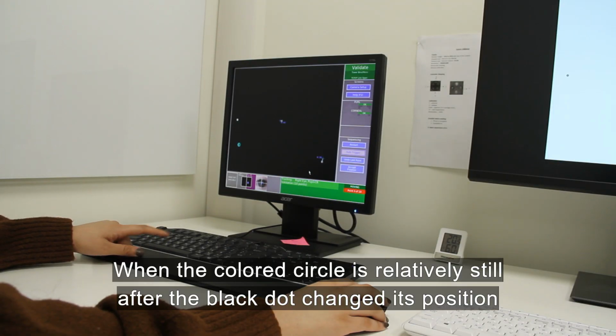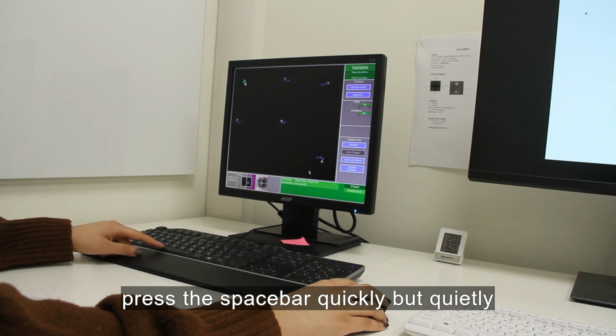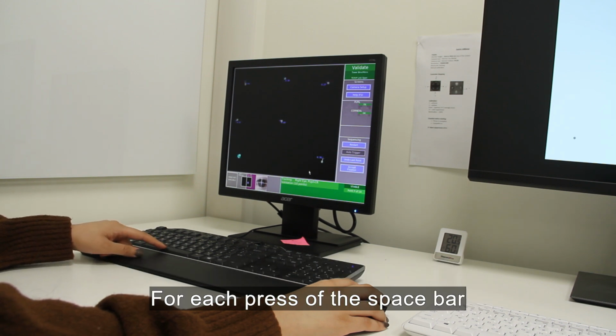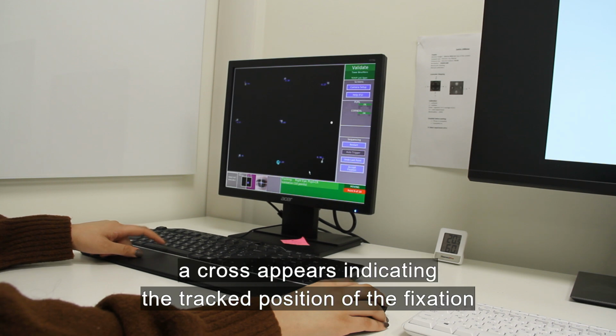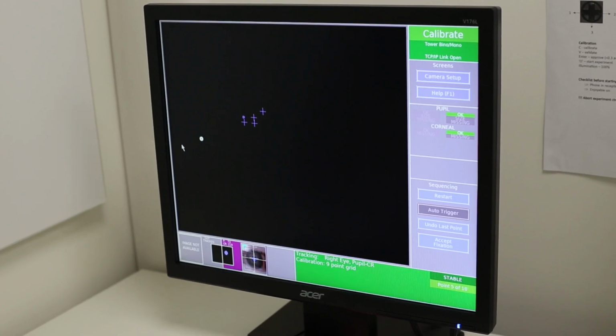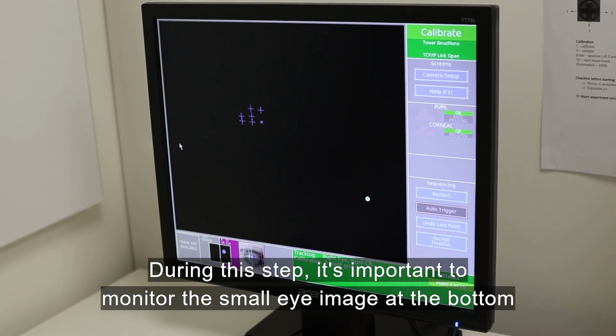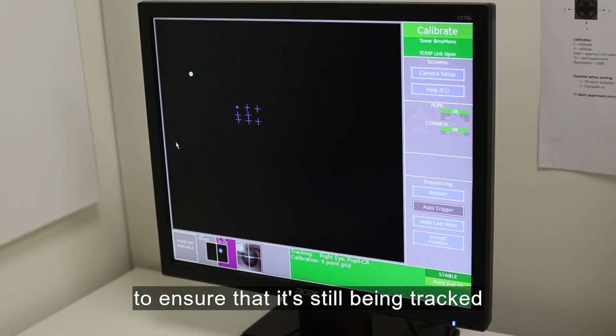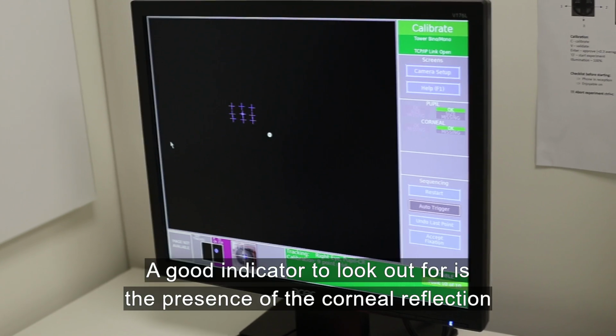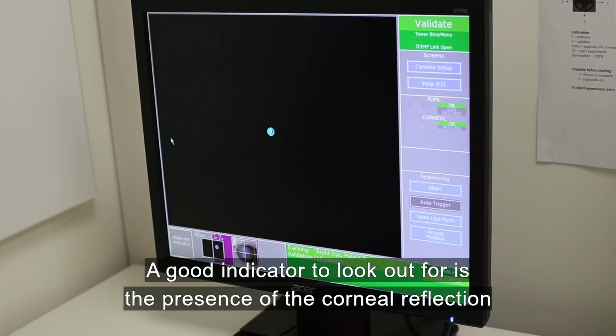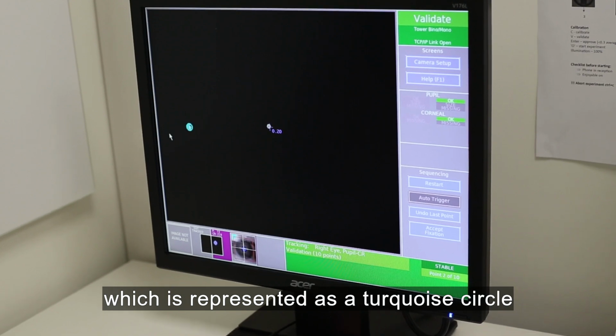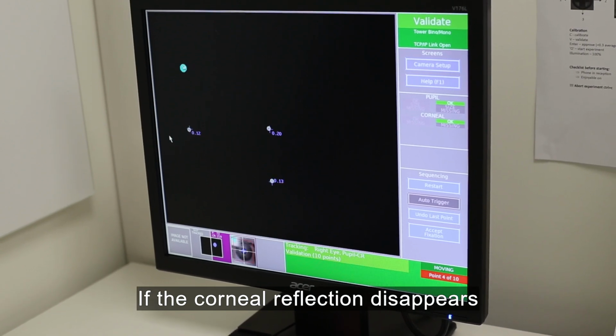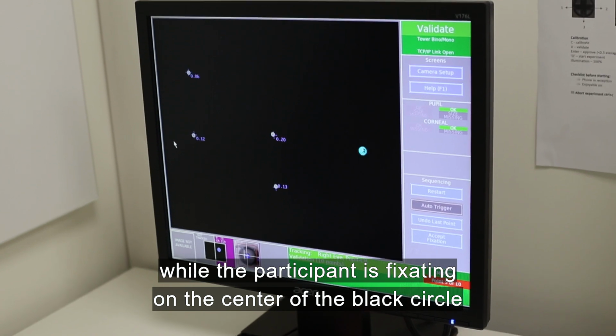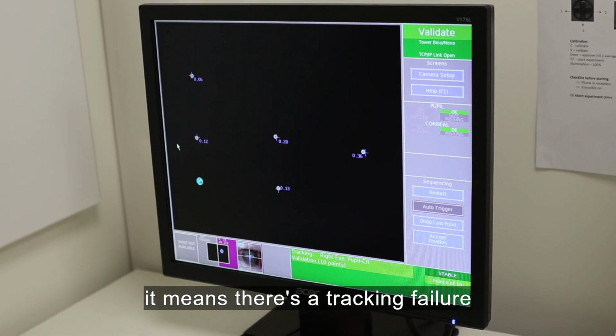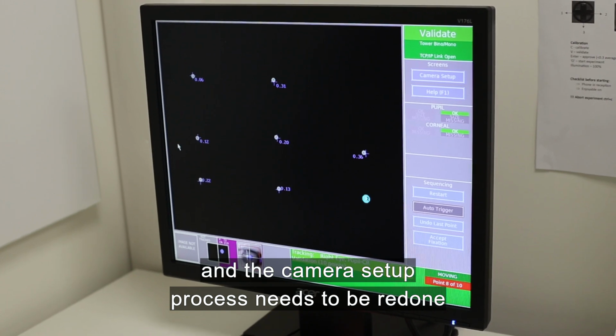When the coloured circle is relatively still after the black dot changed its position, press the spacebar quickly but quietly. For each press of the spacebar, a cross appears indicating the tracked position of the fixation. During this step, it's important to monitor the small eye image at the bottom to ensure it's still being tracked. A good indicator to look out for is the presence of the corneal reflection, which is represented as a turquoise circle. If the corneal reflection disappears while the participant is fixating on the centre of the black circle, it means there's a tracking failure and the camera setup process needs to be redone.